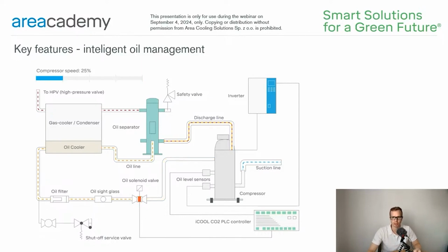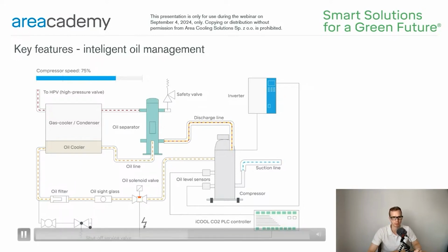The logic is quite simple. The intensity of injection is directly proportional to the speed of the compressor. The higher the speed, the faster the solenoid valve opens and the more oil is injected, as you can see on the visualization. Here we have 75% of compressor speed and the solenoid valve opens more frequently, giving more oil to the compressor crankcase.